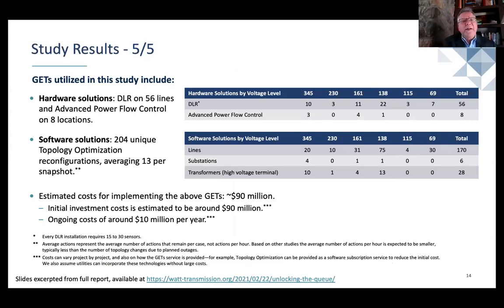With respect to dynamic line ratings, we identified 56 lines within Kansas and Oklahoma that would be good candidates for DLR, spread across the voltage classes in SPP. The majority are at 138 kV, then 161, then 345 kV lines. We also looked at advanced power flow controllers and identified 8 optimal locations for those. Keep in mind we considered advanced power flow controllers as the third option in this optimization effort - had we looked at them as the first option, we'd have a lot more. But we identified 8 applications of advanced power flow controllers to adjust the impedance of lines to push and pull more power across existing assets.